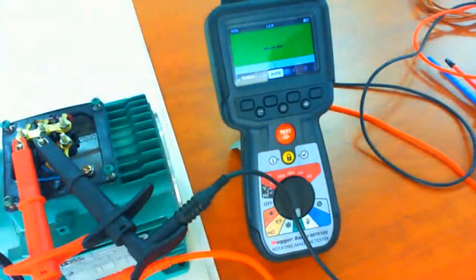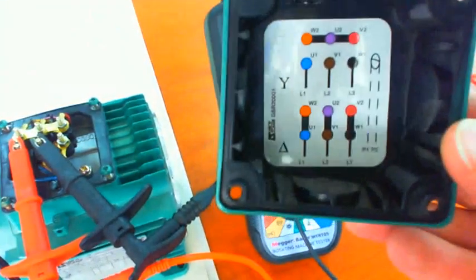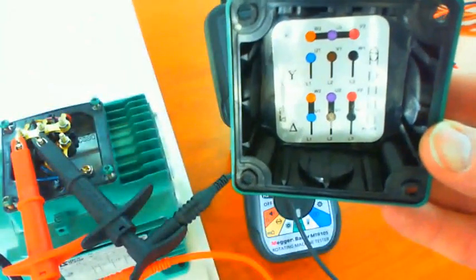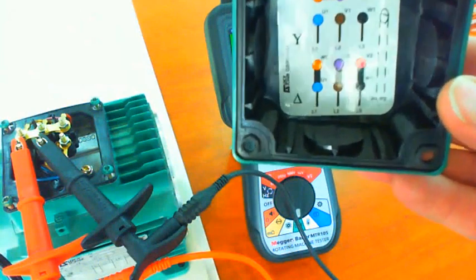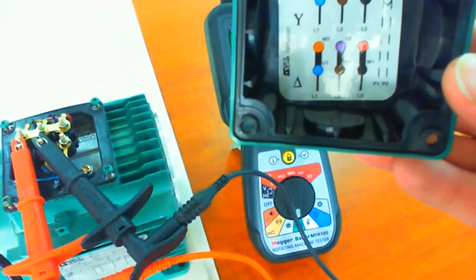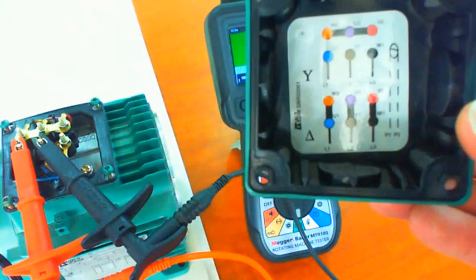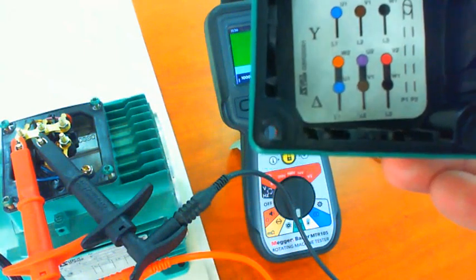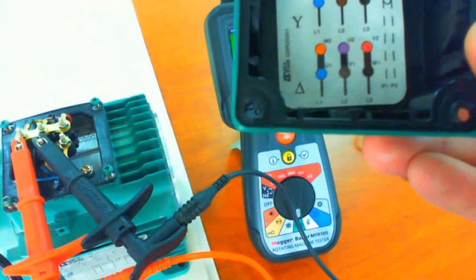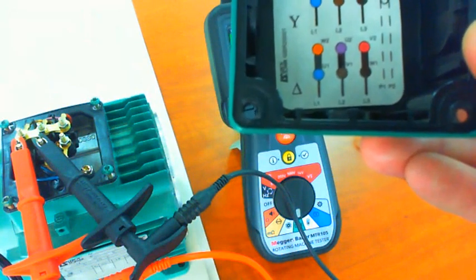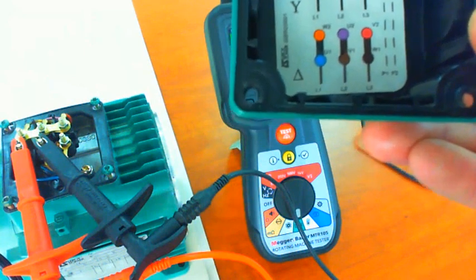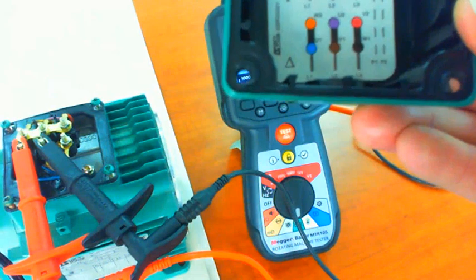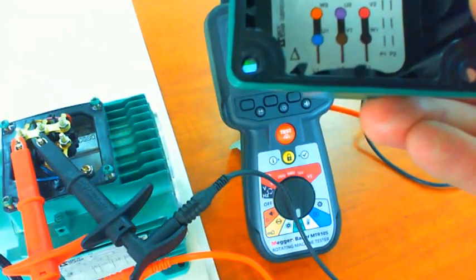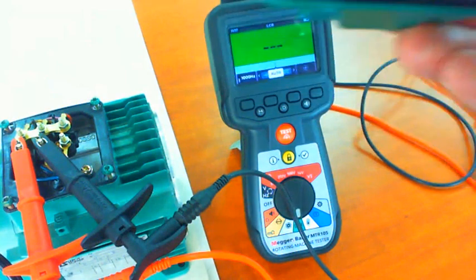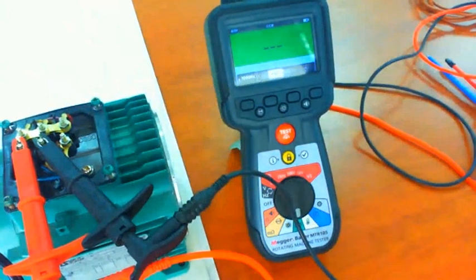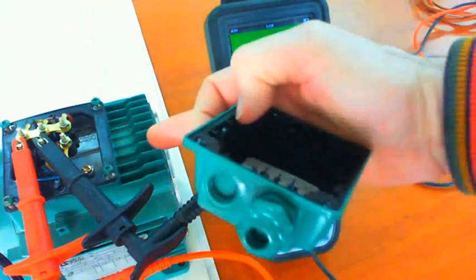Okay, this is a standard motor connection. So if I can just show, hopefully this will focus. With a star connection, which is the top connection, we have got L1, L2, L3, which we're going to connect to those phases. And the star connection is made up of U2, V2, W2. So we've got phase U with the two ends U1, U2, phase V with the ends V1, V2, phase W, W1, W2. To make the star point, the manufacturer uses U2, V2, and W2 connected together with the links, which is what we can see here. So that's what we've got in this motor.